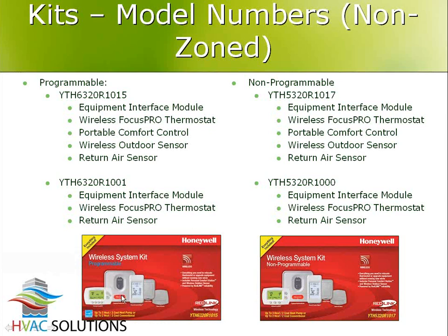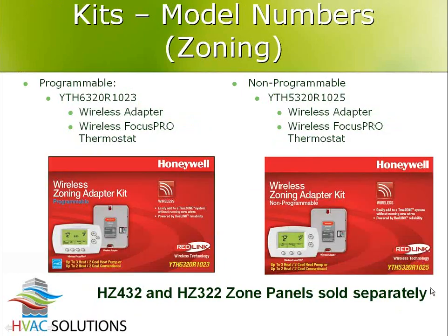Plus, I also have the equipment module that wires in at my furnace. I didn't have that with the Prestige because the Prestige had to wire to the furnace itself. And then I get the return air sensor in case the thermostat should lose batteries. I don't get the return air sensor on the Prestige kit because the Prestige stat does not run on batteries. He has to hardwire for power. And on the right-hand side, it's the same thing, but it's the non-programmable version.